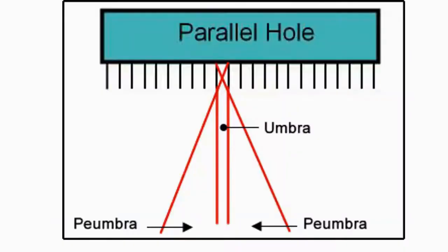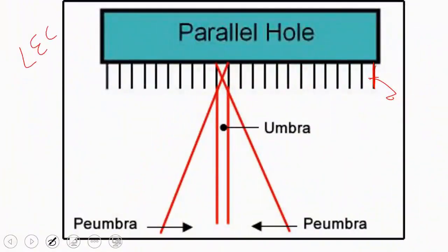This is about the collimator that is fixed, which is the low energy one. Do you remember I was saying that in order to measure energy, in the collimator, the photon that falls on the hole has low energy. This low energy means you don't need a large thickness of the septa to stop it. Therefore, the thickness is small. Okay? If the thickness is small, what does that mean? It means that you will find that the hole becomes significant.